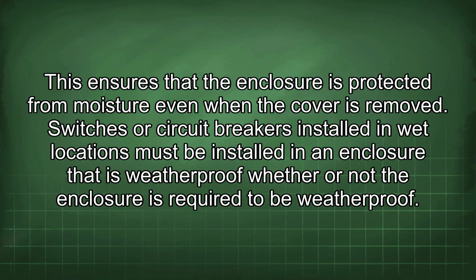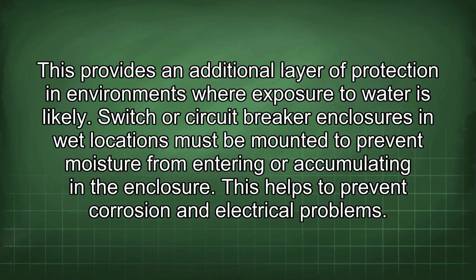Switches or circuit breakers installed in wet locations must be installed in an enclosure that is weatherproof whether or not the enclosure is required to be weatherproof. This provides an additional layer of protection in environments where exposure to water is likely. Switch or circuit breaker enclosures in wet locations must be mounted to prevent moisture from entering or accumulating in the enclosure. This helps to prevent corrosion and electrical problems.